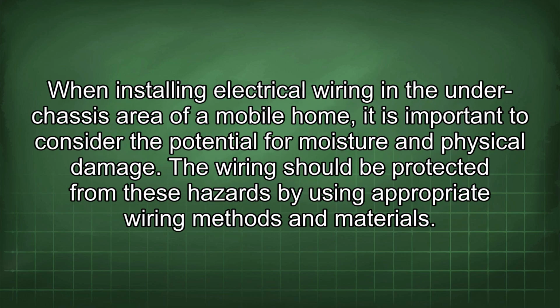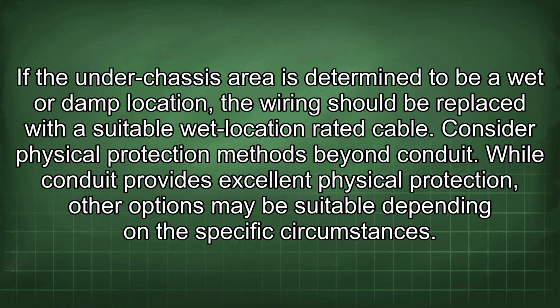When installing electrical wiring in the under chassis area of a mobile home, it is important to consider the potential for moisture and physical damage. The wiring should be protected from these hazards by using appropriate wiring methods and materials. If the under chassis area is determined to be a wet or damp location, the wiring should be replaced with a suitable wet location rated cable. Consider physical protection methods beyond conduit. While conduit provides excellent physical protection, other options may be suitable depending on the specific circumstances.